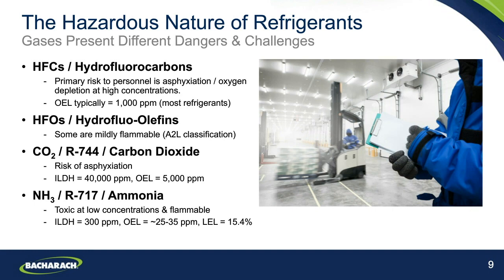It tends to be typically in fairly high concentrations and with a relatively low flame propagation and high ignition temperature, which means we find the A2L classification, which defines these as mildly flammable refrigerants. CO2, of course, is a very old refrigerant and has been coming back into the market more prominently now. We do see regional differences in terms of how widespread the use of CO2 currently is. In particular, in Europe, we are seeing a very high percentage of new systems going in using CO2 as a refrigerant, especially in the food retail industry.